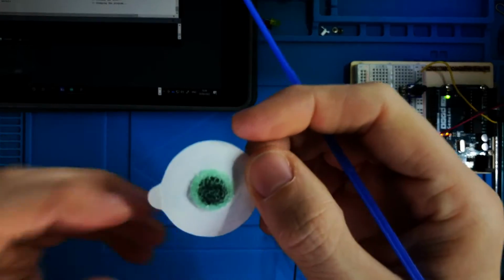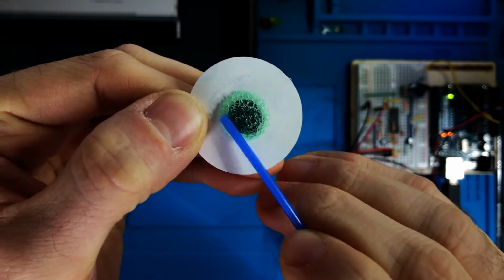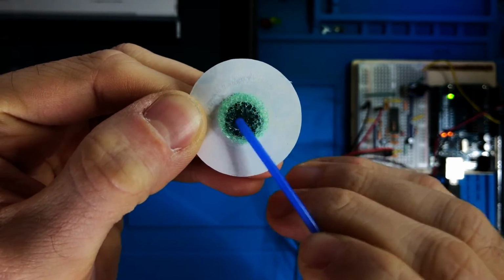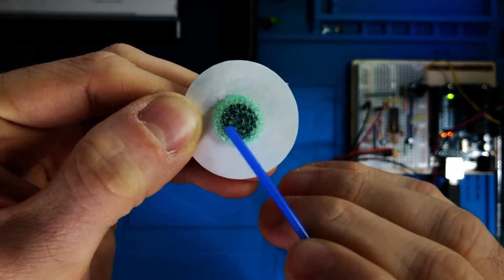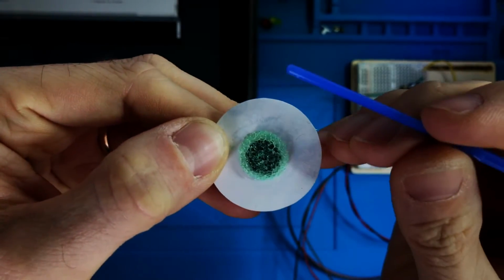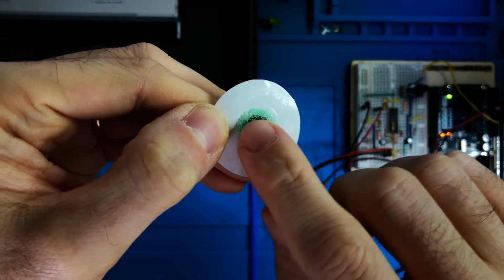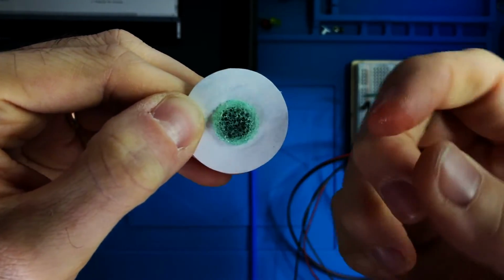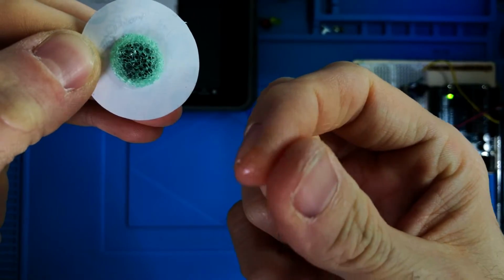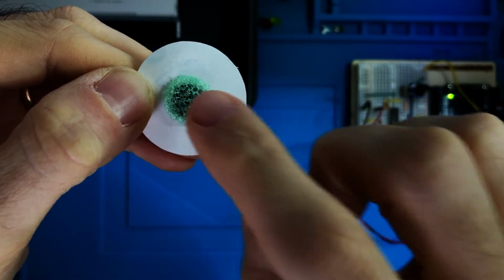So we mix the water with the gel and we try to revive this electrode like this. You see now the water is melting the dry gel. You can also use your finger, there is no danger in doing this. Okay, you mix it like this. Then if you do like this, you will feel that it's a little bit slippery. So this is the gel. Okay, so let's say that one electrode is ready.